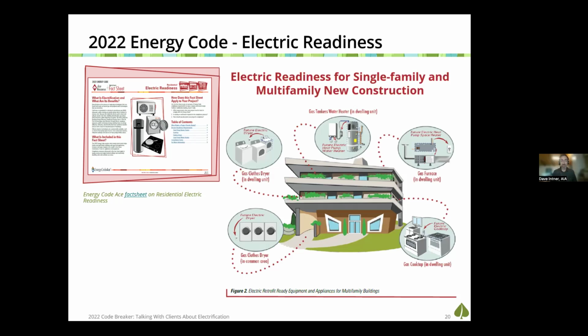Electric readiness is only a provision at this time for new construction. So in the case of a remodel, if you're replacing HVAC or water heating, there's nothing to say you can't do like-for-like right now. You would need to put in minimally compliant equipment on a prescriptive basis. So say you put in a gas furnace, it would need to meet minimum efficiency requirements, as well as other things that might get triggered, like duct testing on a ducted system, and other code-required features. But you would not be required in a like-for-like change-out to put in a heat pump, unless your jurisdiction has adopted a REACH code, and you don't need to do electric readiness at that time because you're not really doing anything to the electric system.